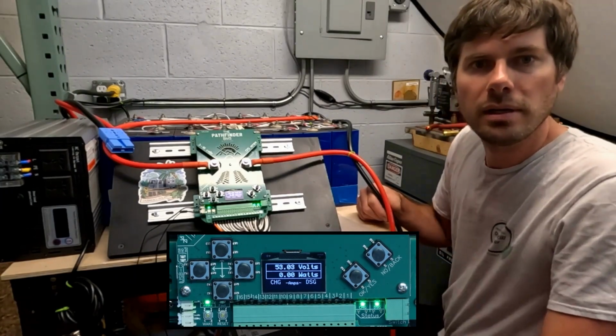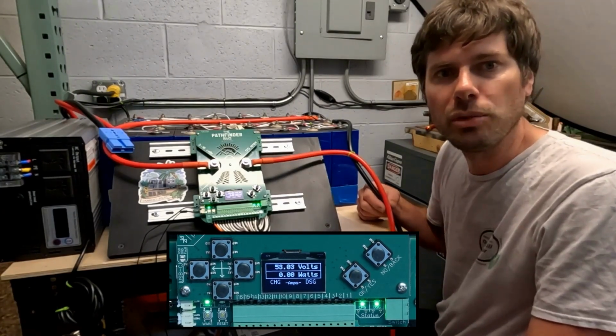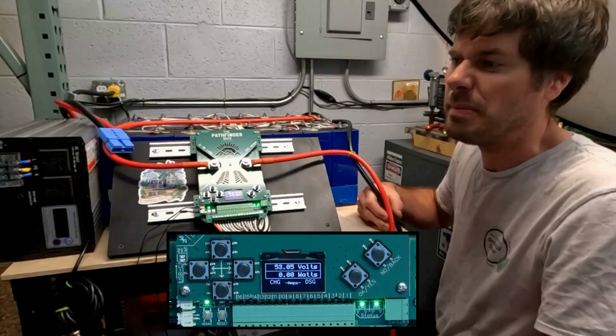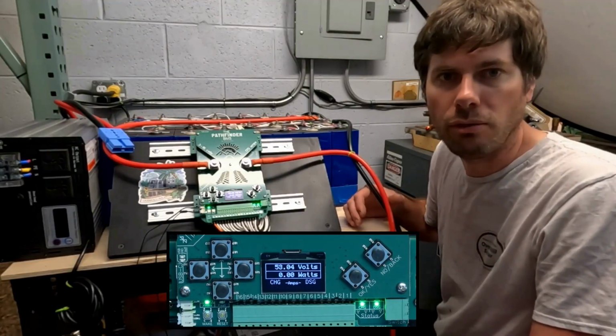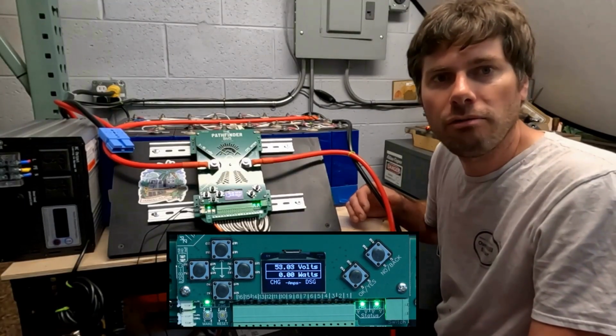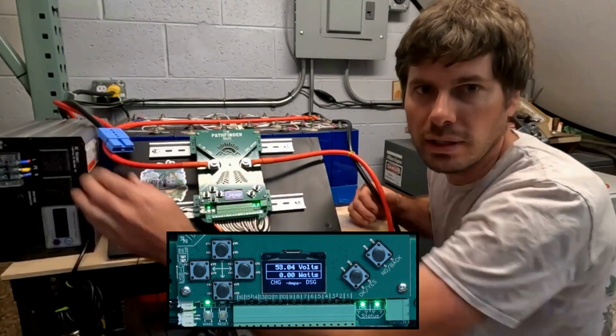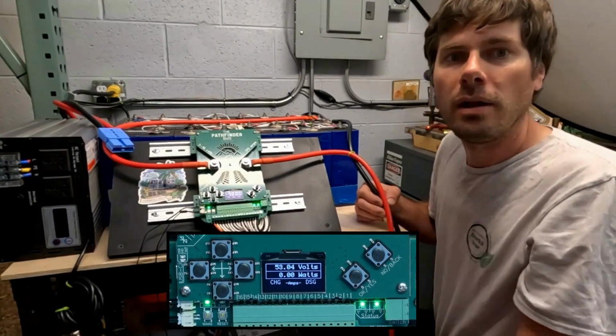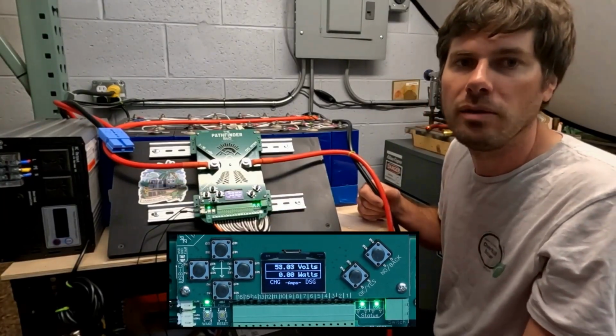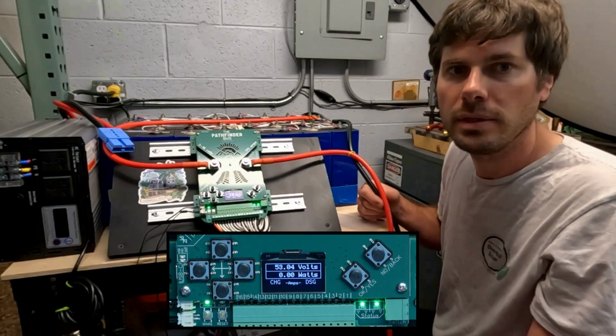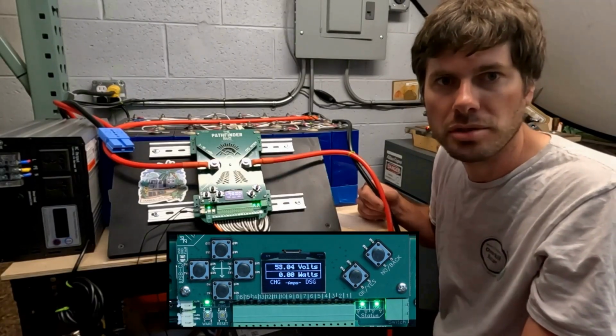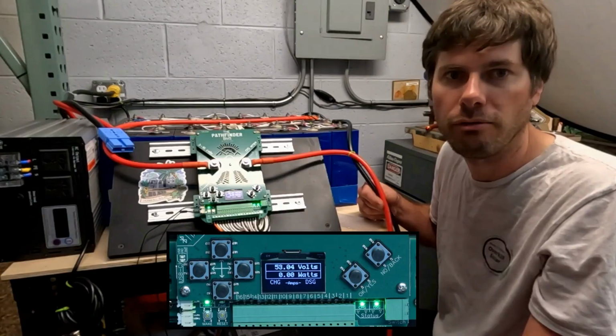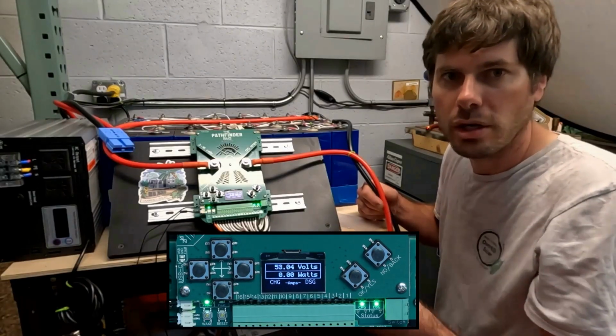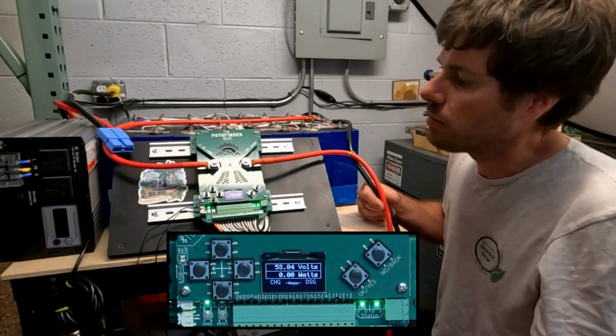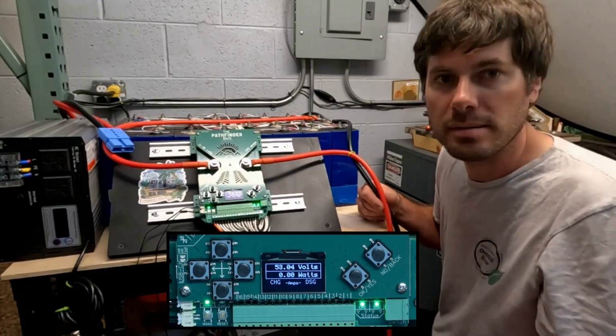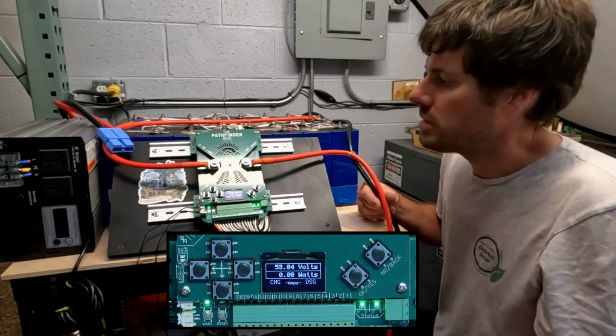This is going to be a quick demonstration of the pre-discharge mode on the Pathfinder BMS. What pre-discharge is good for is if you have a large inverter like this one connected to your system. They all have a big capacitor bank, and when you connect them directly to your system, usually the BMS will detect a short circuit as the inrush current for the capacitors charges up. So what the Pathfinder BMS has built in is a pre-discharge circuit.